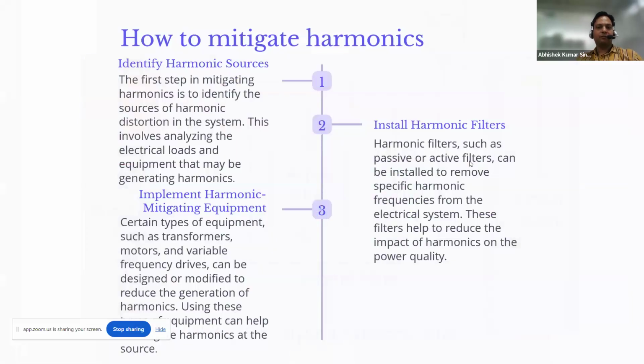Now, how to mitigate harmonics? There are multiple ways to mitigate the harmonics. First of all, as we discussed, whatever the sources of harmonics are, like the loads, just plan to put the filters near the source. Second point is the harmonic filter. We can plan to have a harmonic filter, which can be a passive filter or an active filter. We will discuss both in our further slides, what is a passive filter and what is an active filter, and which one is better to have in the system. And then implementing harmonic mitigating equipment. This is almost the same as what we discussed.